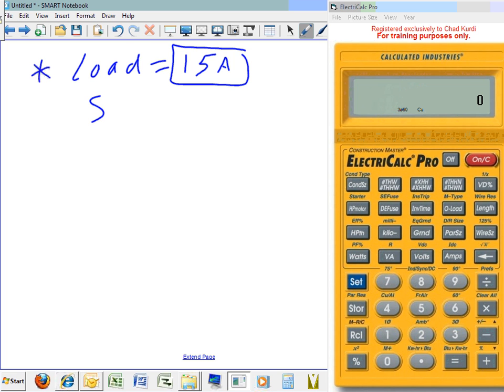Size conductor, knowing that there are 16 current-carrying conductors. I know that there's 16 of them, and I decided I will use 15 amps. I want to see if I ask the calculator, I need 15 amps, would I end up with number 12? I should end up with number 12 conductor. Let's go ahead and do it, and it will size based on 16.